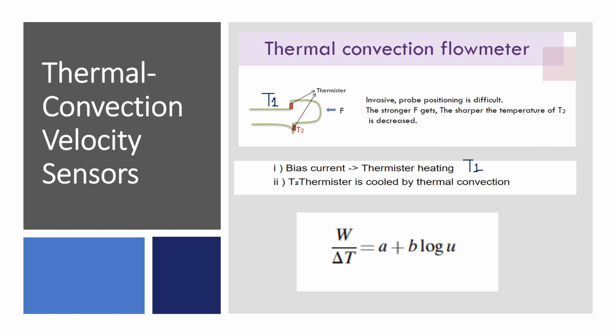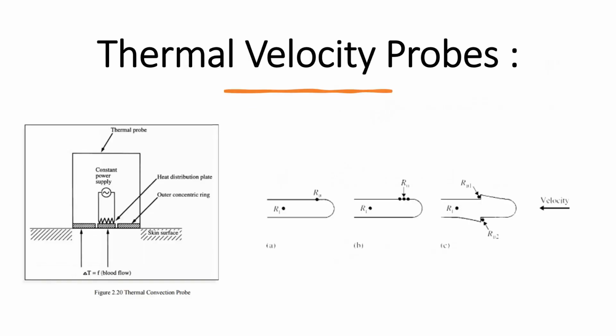The thermistor T1 is heated to a temperature difference delta T above blood temperature by the power W dissipated by current passing through T1. These quantities are related to blood velocity U by an equation where A and B are constants. The thermal velocity probes are shown here. By using these probes, the rate of heat removal from the tissue under the probe is measured. RU is the velocity sensitive thermistor and RT is the temperature compensating thermistor.